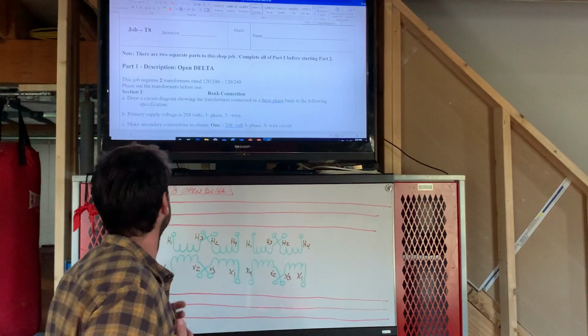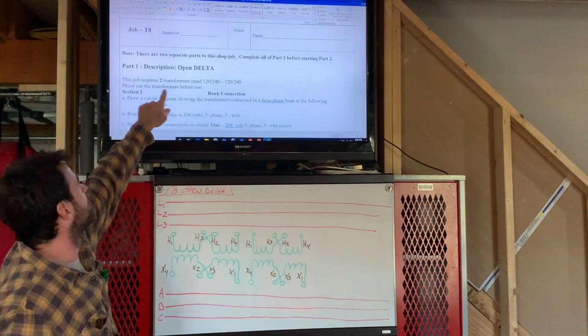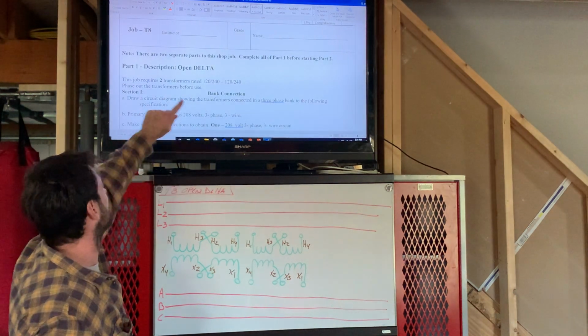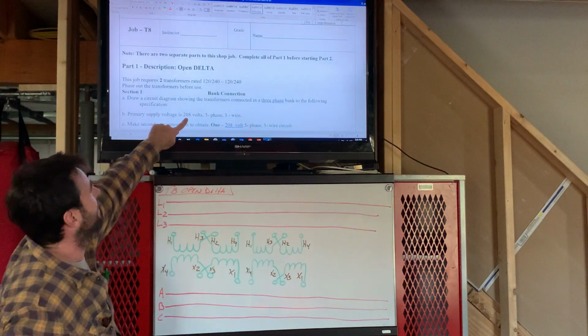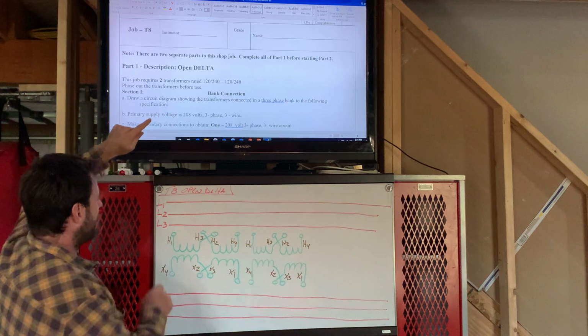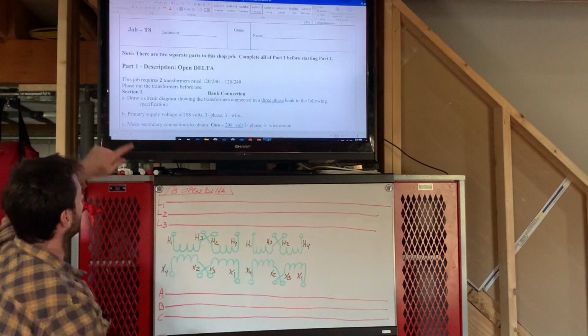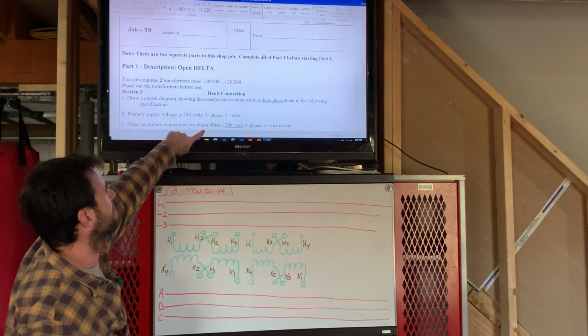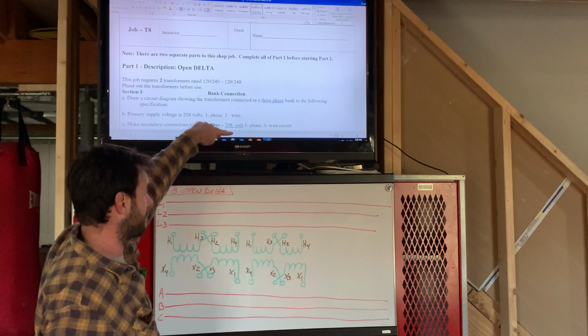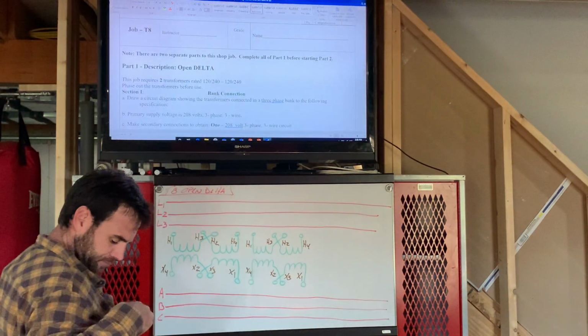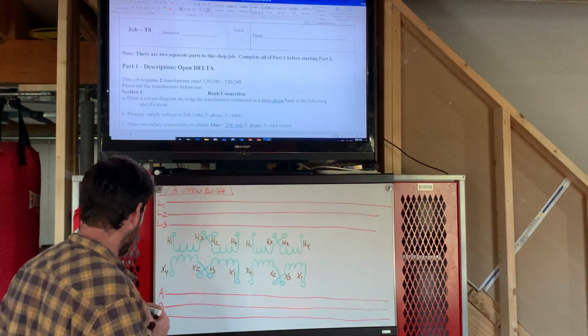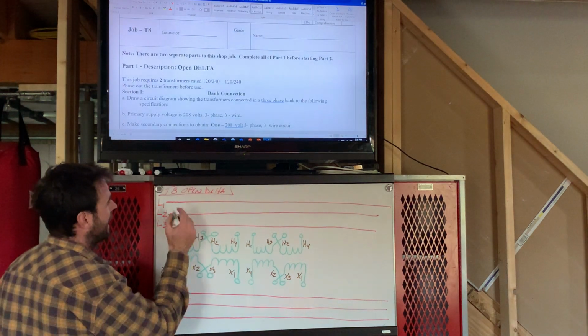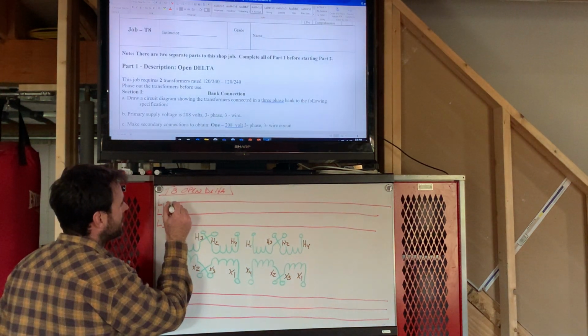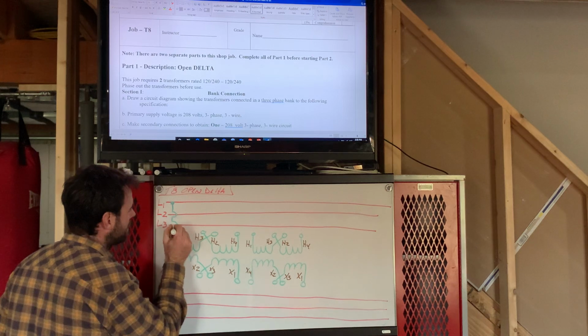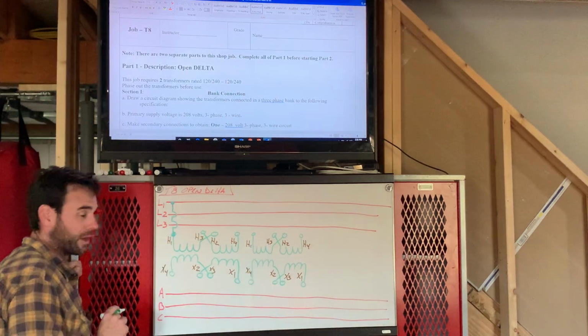So right now, T8, open delta. This job requires two transformers. We're going to have primary supply voltage of 208 three-phase 3-wire, and we make secondary connections to obtain 208 three-phase 3-wire. So, how we're going to do that: first, we're going to come out of line 1, come down, we're going to go to H1.